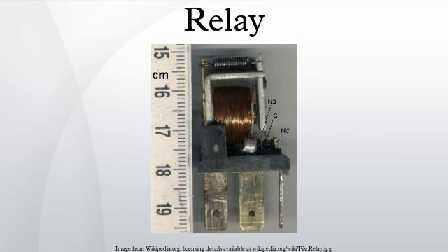This contact degradation drastically limits the overall life of a relay to a range of about 10,000 to 100,000 operations, a level far below the mechanical life of the same device, which can be in excess of 20 million operations.